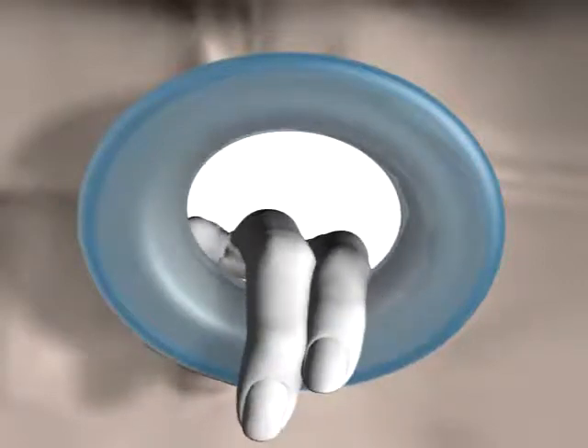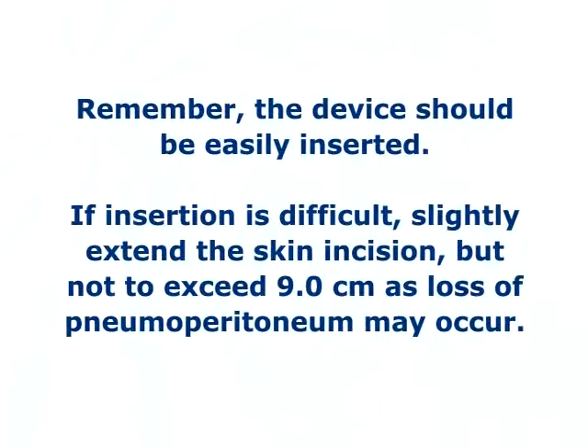Verify the device seating with an endoscope. Remember, the device should be easily inserted. If insertion is difficult, slightly extend the skin incision, but not to exceed 9 cm as loss of pneumoperitoneum may occur.